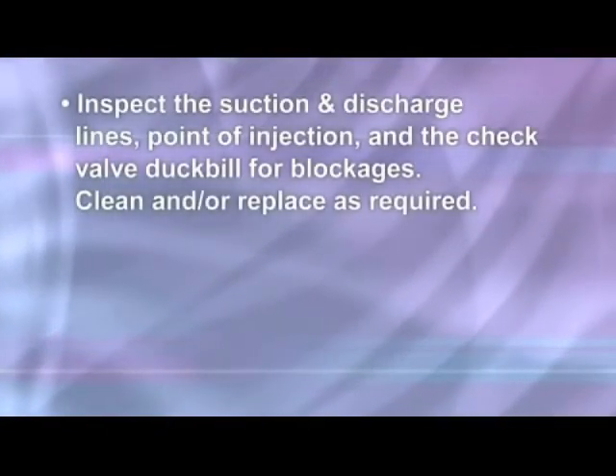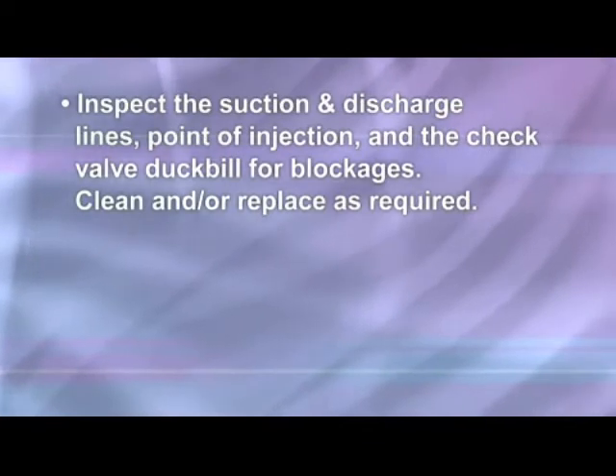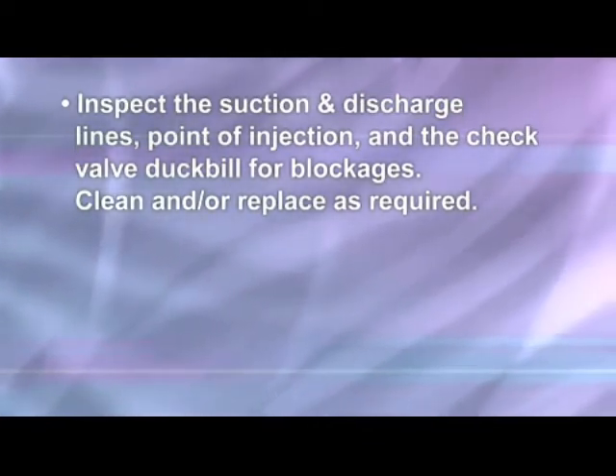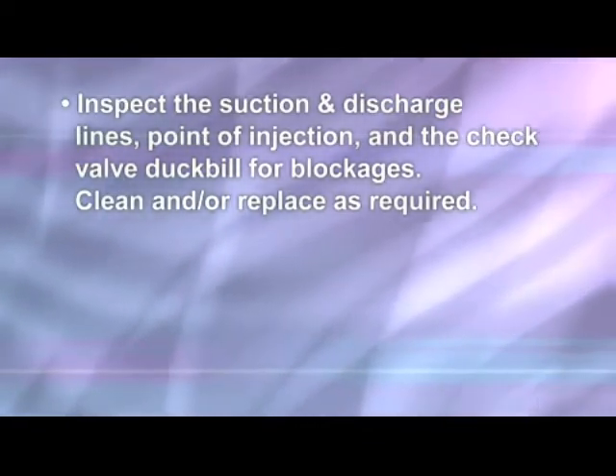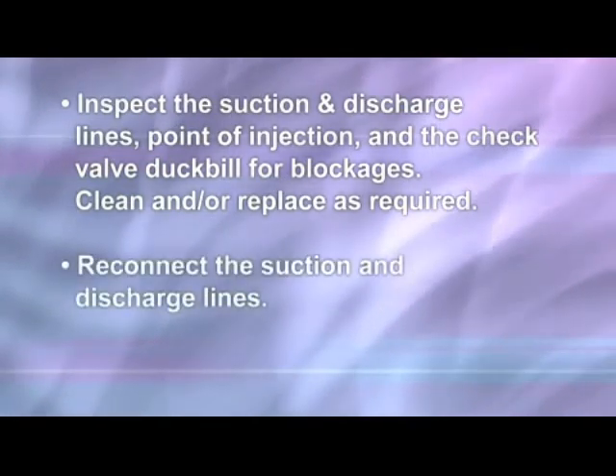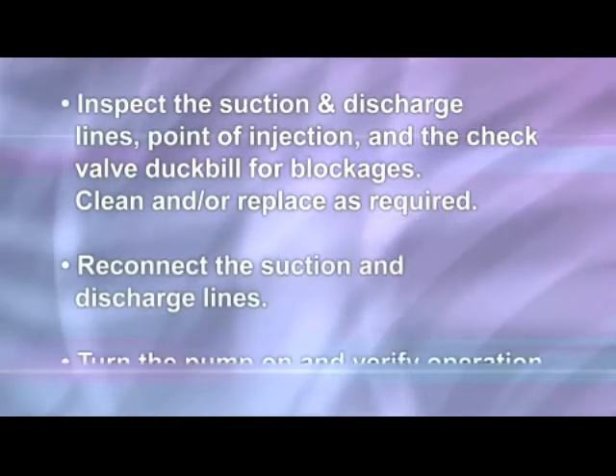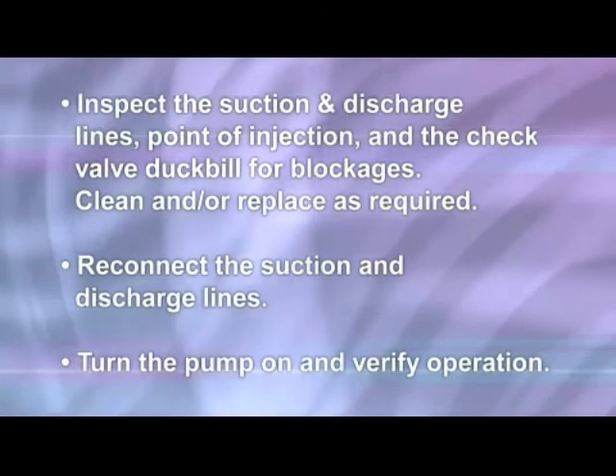Inspect the suction and discharge lines, point of injection, and the check valve duckbill for blockages. Clean and/or replace as required. Reconnect the suction and discharge lines. Turn the pump on and verify operation.